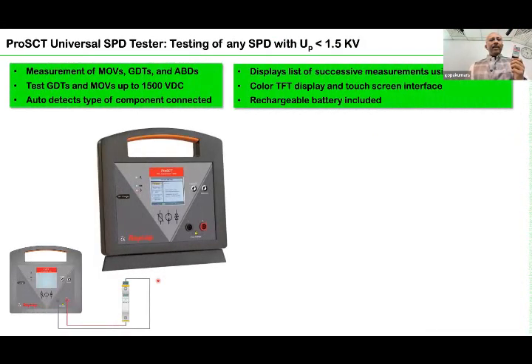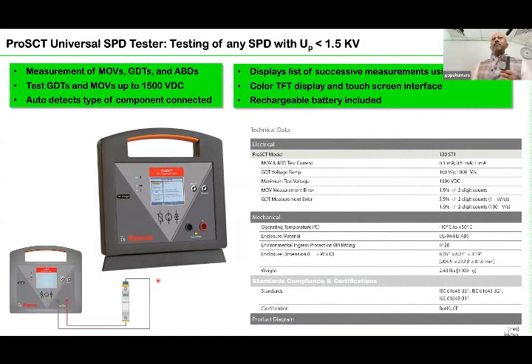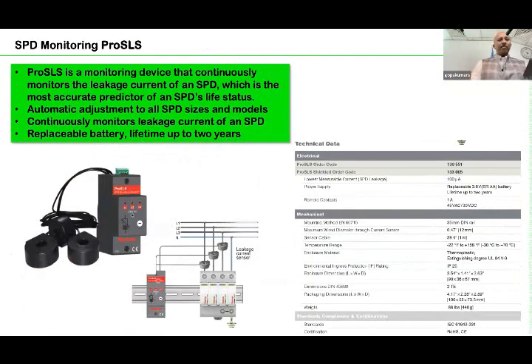Then there are other devices available. We call it a universal SPD tester. With this tester, you can find out the spark over voltage of a spark gap, or the clamping voltage at 1 milliampere, or the clamping voltage of an MOV. So with this device, you can find out whether the SPD is really working or not. We use these devices to test SPDs. This is also a good device.